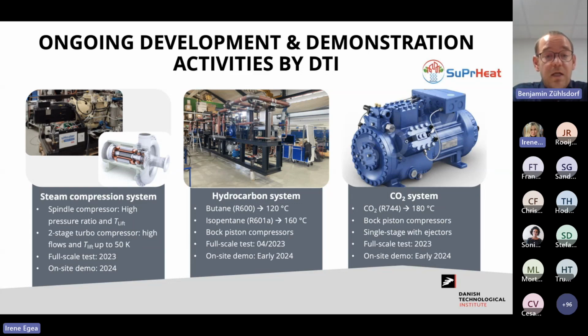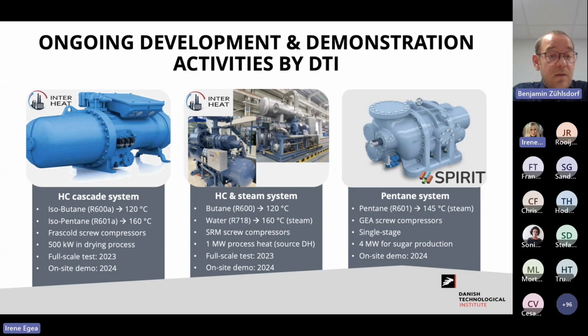And then if we go to the next slide, there's just 3 more examples. The first 2 are from a Danish project, also with some international partners. It's different compressors. It's screw compressors, 120 degrees, 160 degrees, also with hydrocarbons, isobutane, isopentane. It's Frascold compressors in this case, and this will be integrated in a drying process. It can also supply this 120 to 160 degrees. And then there's another one. Actually, it's the same temperature ranges, up to 120, 160 degrees. It's SRM compressors, a bit larger capacities, and it's steam compression here.